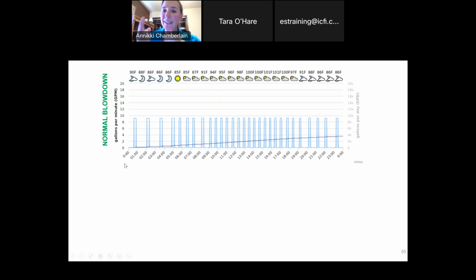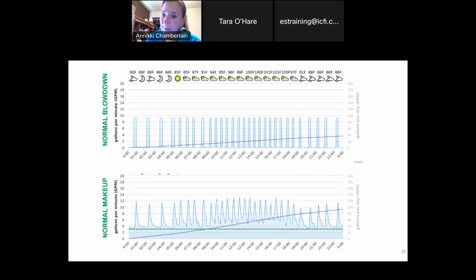But here you can see this is 1 minute resolution on a cooling tower. So what I can see here, we have our gallon per minute flow on the y-axis. On the x, we have our time of day. So I can see this beautiful normal blowdown pattern. The mineral concentration gets high, the tower blows down for a set amount of time, mineral concentration gets high again. This is really beautiful. Everything's operating as normal. Then if I compare it to my makeup, same thing. Every time the tower drains, I've got a nice makeup that comes in behind it. Always have a little bit of flow to keep up with evaporation, but this is a beautiful, healthy cooling tower right now.